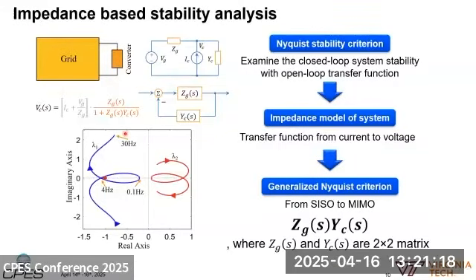We can see that the system stability is determined by the denominator of this formula, which is 1 plus the impedance of the grid times the admittance of the grid-type converter. This term is called the return ratio, and it's of interest to us.